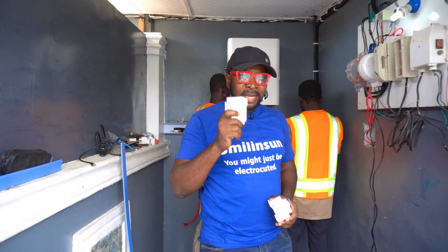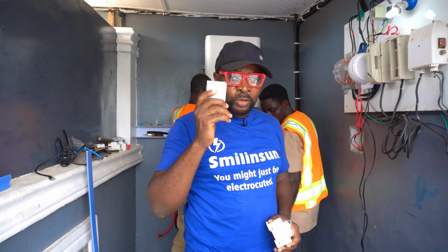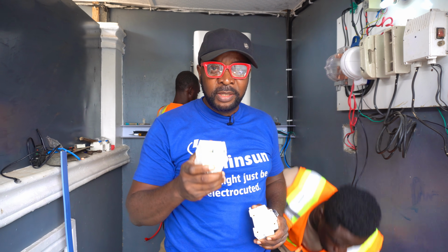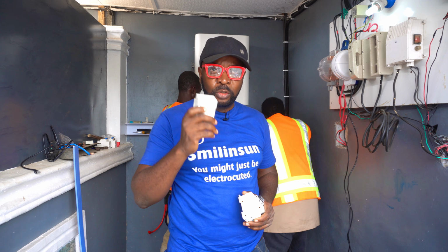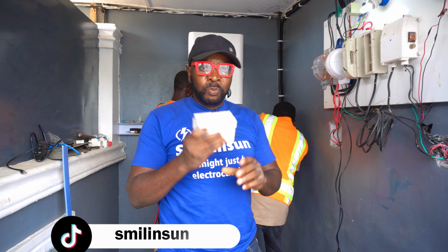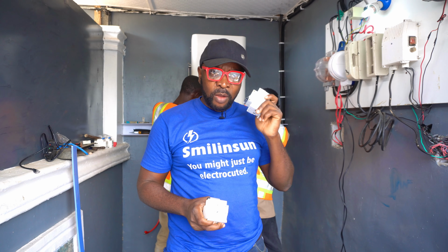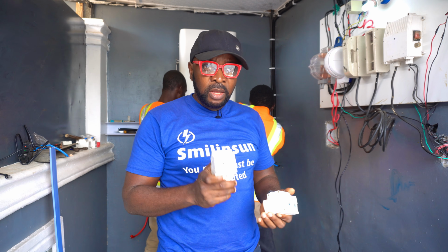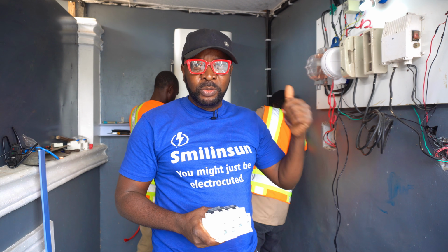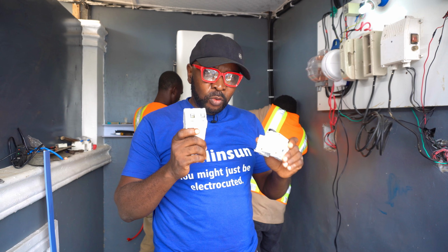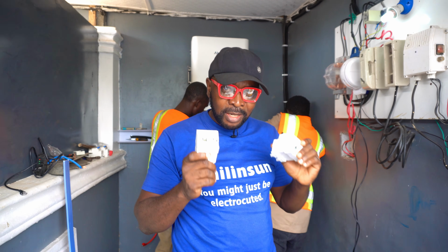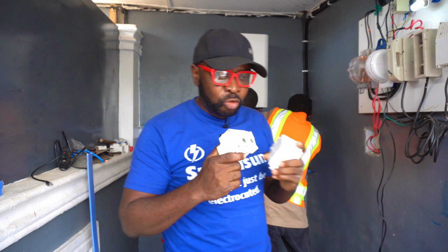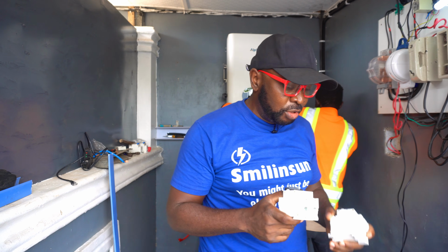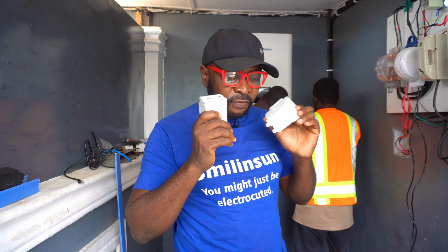If the solar panels exceed 500 volts, this circuit breaker is going to turn off. The same applies to current - if it's above 32 amps, it shuts off. This particular one was perfect for low voltage, but won't work for high voltage because its rating is 125 amps by 1000 volts. That's too much, because the solar panel is going to be outputting 500 volts, so it won't be able to respond and trip when it's mostly needed - it's meant to kick in and trip off to avoid any damage to the system. So this will definitely have to be replaced.